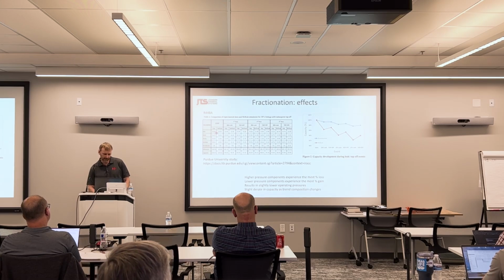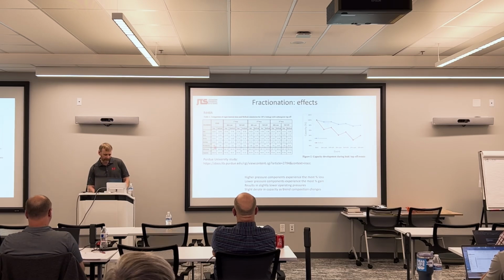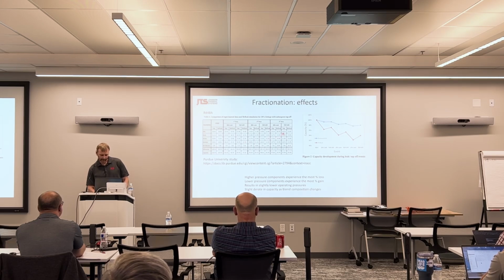It consists of 26% R32, 26.1% R125, 20.9% R134A, 20% R1234YF, and 6.9% R1234ZEE. After the third cycle, if we compare this column over here to the original, basically you can see that we went from 26% R32 to about 24% R32. So our higher pressure component was leaked out, and we've got about 2% less R32 after the third leak and recharge.